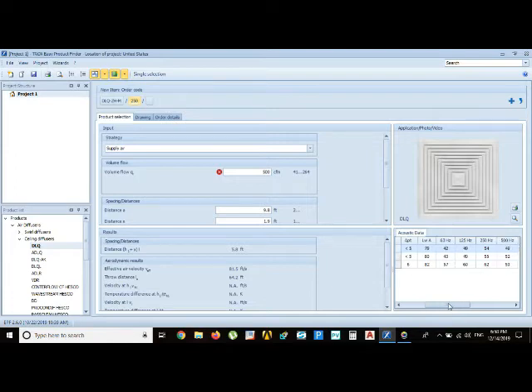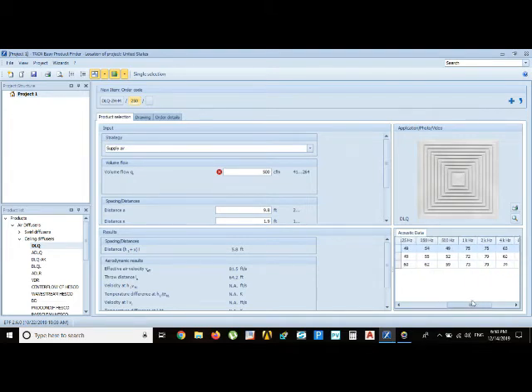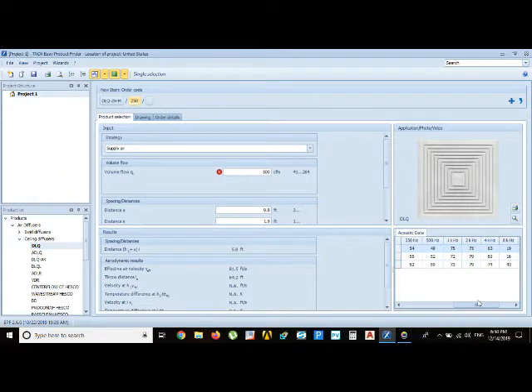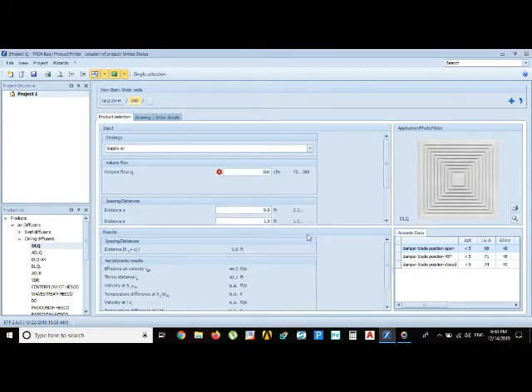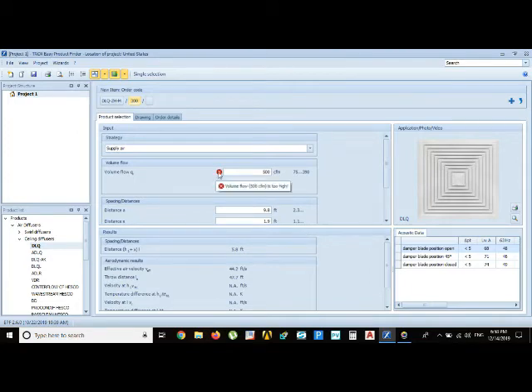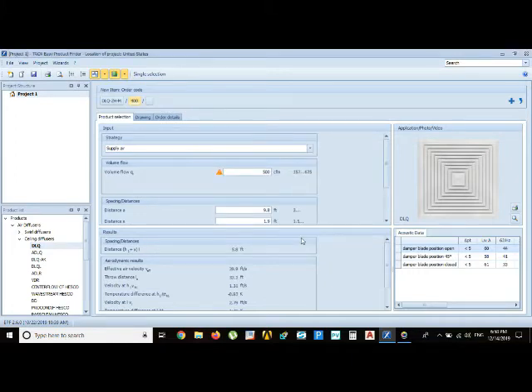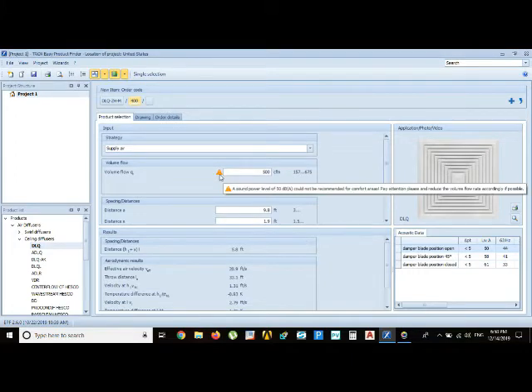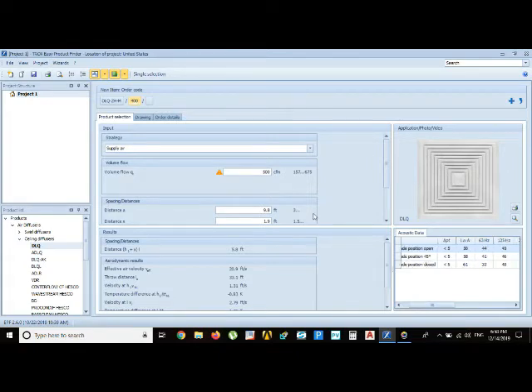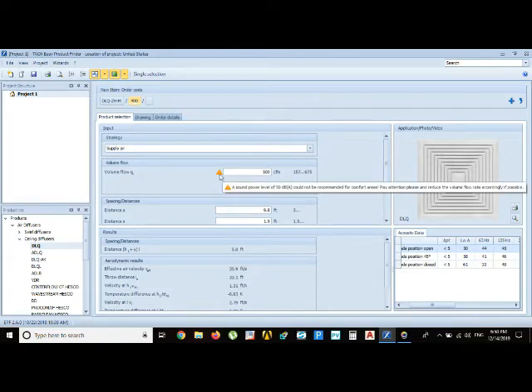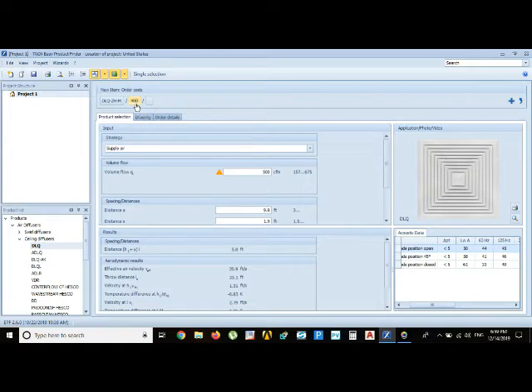You can see here the noise level is increased up to 79 in 63 Hz, 40-49, 54. You can see it is not recommended, it's not standard. Just select the 300. Let's see, is it suitable for this or not? No, it's also not suitable for the 500 CFM. Then select 400. Sound power level of 50 decibels, sound level is increasing. It's also not suitable, but you can use this in certain areas where the sound level is not recommended. But it is standard to keep the sound level below 50. 35 is optimum.